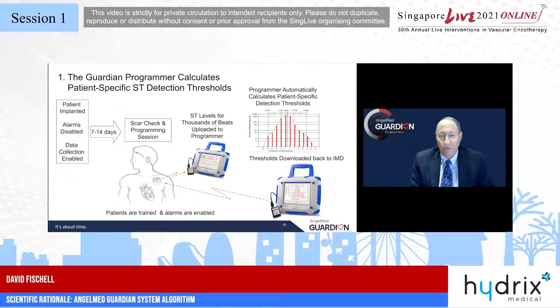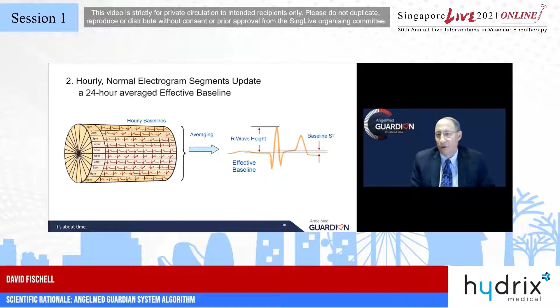To allow for accurate detection and avoid false positive events, it is important to detect acute ST changes by comparing what is happening in real time with what is normal for the patient in the recent past. The second machine learning method involves having the IMD learn what normal ST levels look like over the last day by creating an effective baseline from 24 hourly collected electrogram segments. Once an hour, a new 10-second electrogram is added to the baseline collection, and the average effective baseline is updated. It supplies for comparison with newly collected data a baseline ST level set as a percentage of the average R wave height for the 24 collected segments.